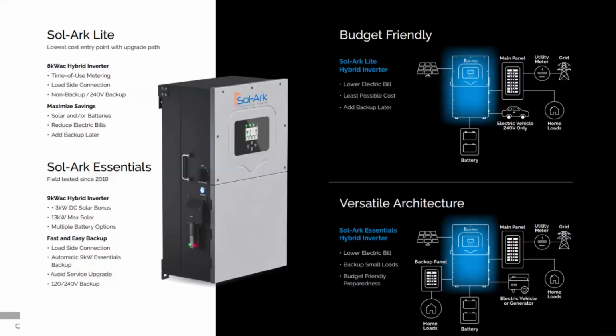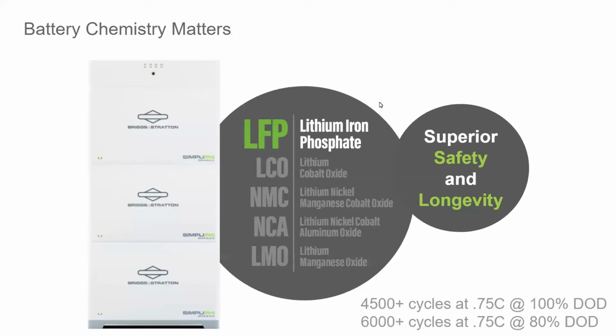But it's also a good inverter if you want to, say, expand an existing system. If you have older batteries and you want to expand the battery bank, even if they're the same make and model, you can't always put old batteries with new batteries and have good product life. So the Sol-Ark Lite can run in parallel and do demand management, thereby expanding a bank.